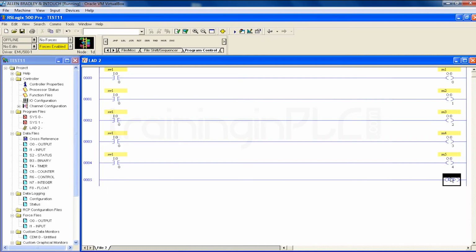So on only those 2 days you need to skip these 2 rungs, right? There is no need to change the program for those 2 days. You can make use of the jump instruction so that it will skip these 2 rungs as per the requirement. So if you want to skip these 2 motors, you need to introduce the jump before M3 and you need to finish the jump after M4, or before the start of M5.